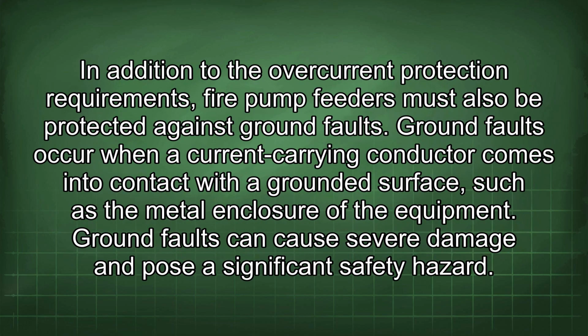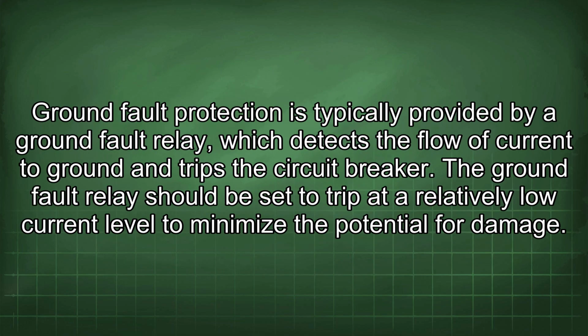In addition to the overcurrent protection requirements, fire pump feeders must also be protected against ground faults. Ground faults occur when a current-carrying conductor comes into contact with a grounded surface such as the metal enclosure of the equipment. Ground faults can cause severe damage and pose a significant safety hazard. Ground fault protection is typically provided by a ground fault relay, which detects the flow of current to ground and trips the circuit breaker. The ground fault relay should be set to trip at a relatively low current level to minimize the potential for damage.